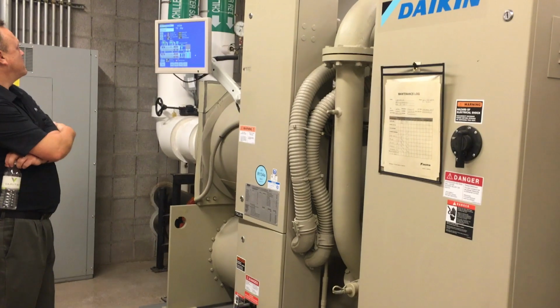Also, I would argue that the space for the outdoor condensers is going to be less than your chillers, your boiler, your cooling towers, and your air handlers combined, because each space has its own fan coil, which, depending on the fan coil that you use, is either a high wall or a cassette, and maybe at the largest an 8-ton fan coil. It's going to be a lot smaller than a huge air handler. So you've got the advantage of using a fan coil for each space, and then each outdoor unit is going to be much smaller than your cooling tower, air handler, whatever else you have up on the roof. And you get rid of pumps, you get rid of VFDs for those pumps. If you ever walked into a mechanical room with all the chillers and the pumps, it takes up a lot of space. And if you compare that to a VRF system, it's definitely a lot less space.